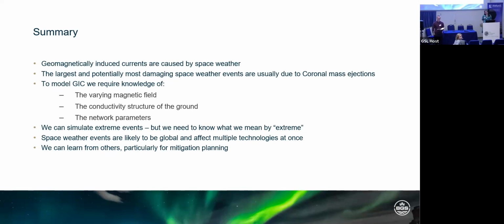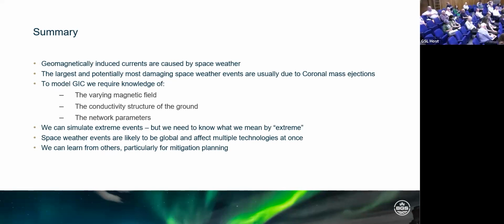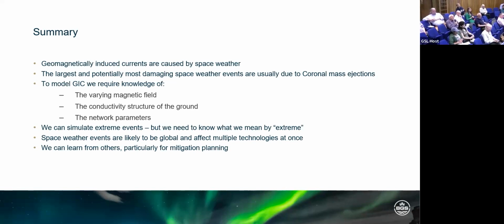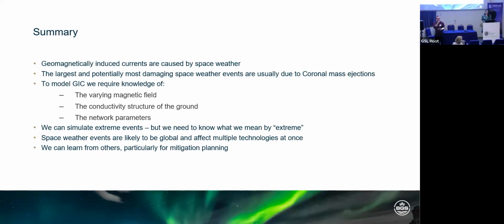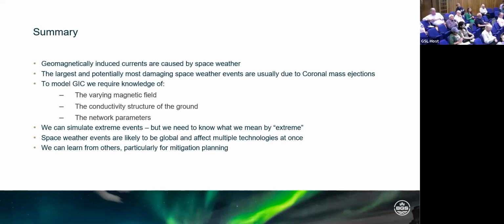You talked about currents in the transformers, but surely the timescales for which transformers are potentially damaged depends on the rating of the transformer. If I've got a transformer with 10,000 amps capability, then 1,000 amps is going to be far less of a problem than if it's 1,000 amps capability. So how does that work? I think there's obviously some more work that needs to be done there.